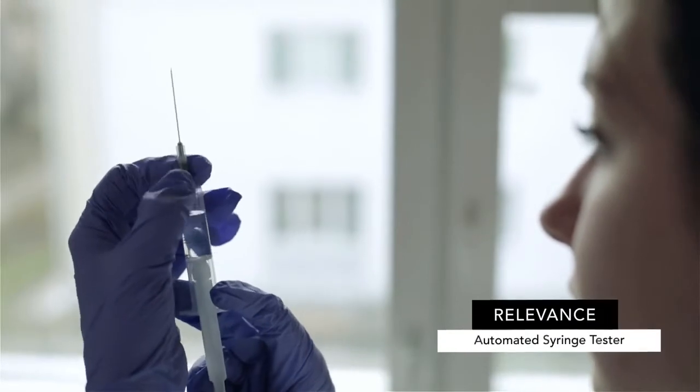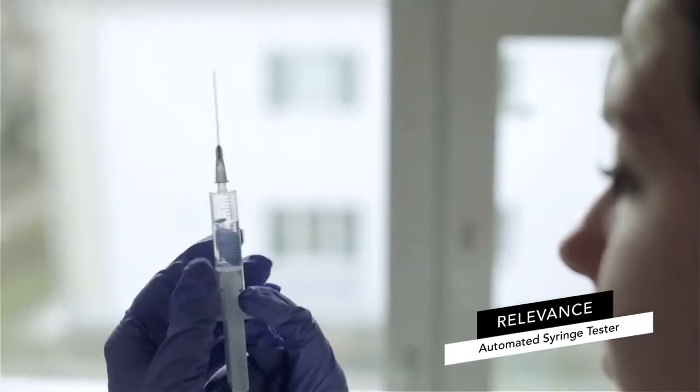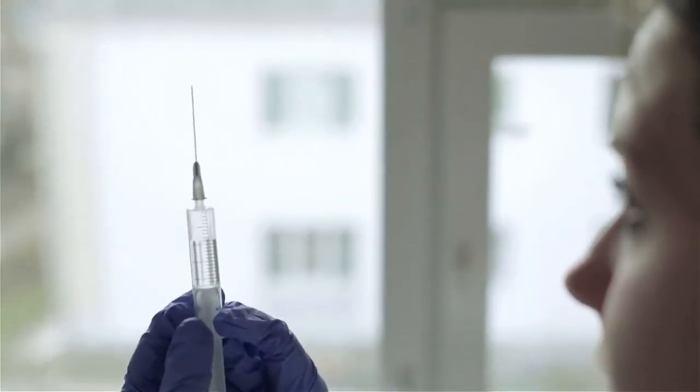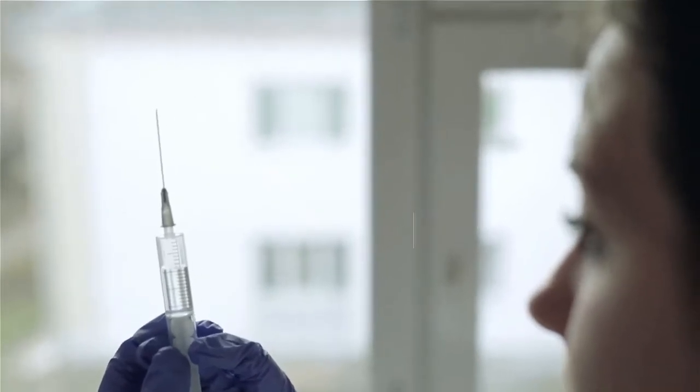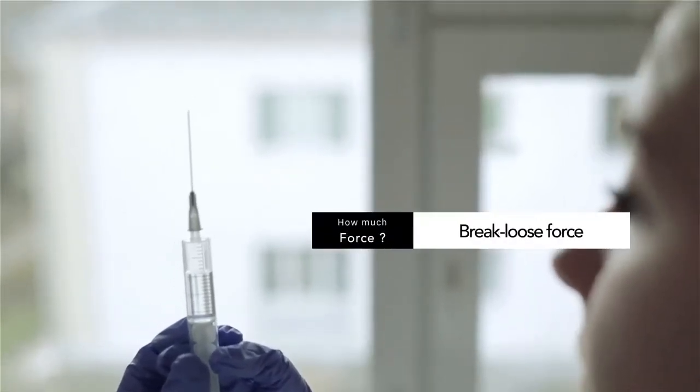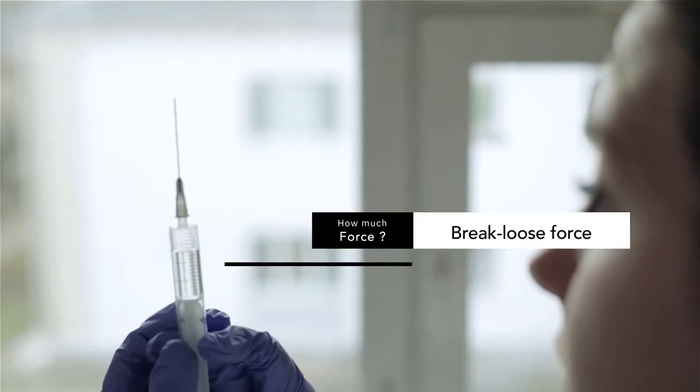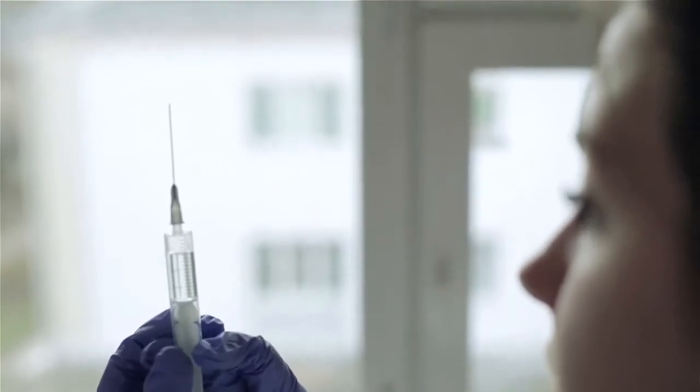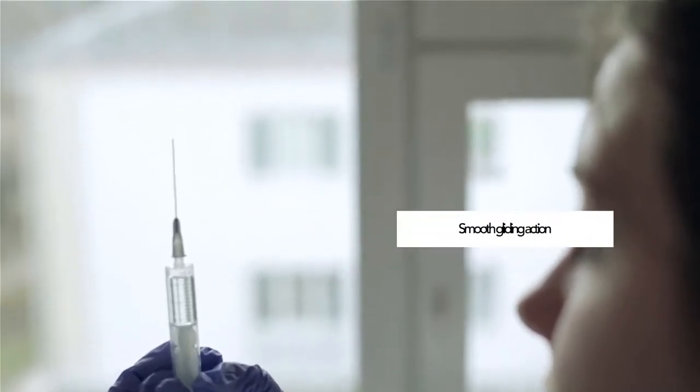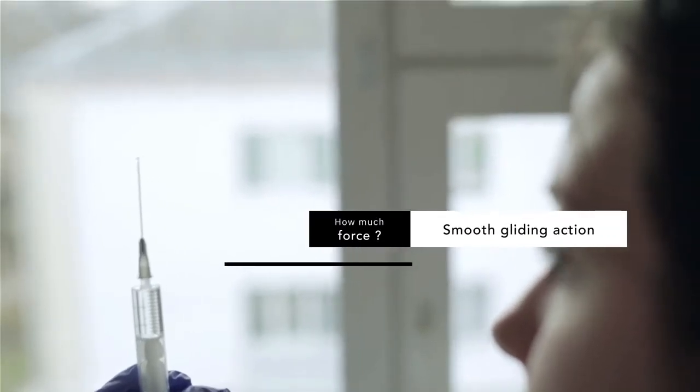Checking the performance and functionality of a syringe is critical with physical testing being high on the list. How much break-loose force does it take to initiate movement of the plunger? Once the plunger is moving, does it have a smooth gliding action to safely and consistently inject the drug without causing discomfort to the patient?